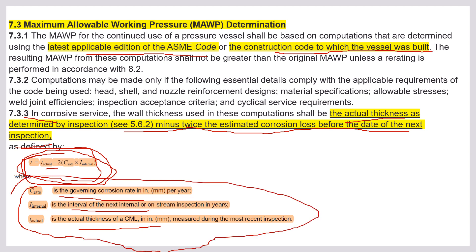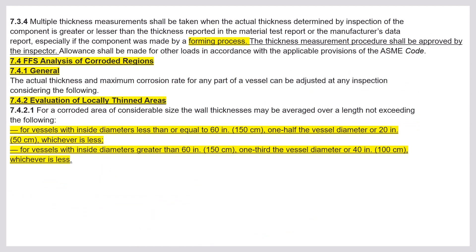Multiple thickness measurements shall be taken when the actual thickness determined by inspection is greater or lesser than the thickness reported in the material test report — especially if the component was made from a forming process. In a forming process such as rolling or pressing, the thickness will vary and may not come out uniform. The thickness measurement procedure shall be approved by the inspector, and allowance shall be made for other loads in accordance with applicable ASME code provisions and FFS analysis for corroded regions.